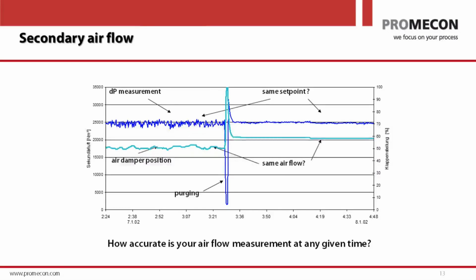And what you can basically see here is the secondary air to one of these burners. And the dark blue line that you can see is the secondary air measurement by delta pressure. Now, when you look at this line, you can see that it's more or less divided into two. On the left-hand side, it is a bit noisy, and on the right-hand side, it's much more smooth. What happens in between is basically a large gap where someone cleaned the impulse line and therefore made a much better transmission of the delta pressure to the DP transmitter possible again. So you can see the noise of the left side is gone on the right-hand side. However, the level of the measurement, which is 25,000 cubic meters per hour, that level has not changed. There is no change in the level of flow. But if you look below to the damper position, that light blue line, you can see that not only the noise gets less, but the level of the damper completely changes.